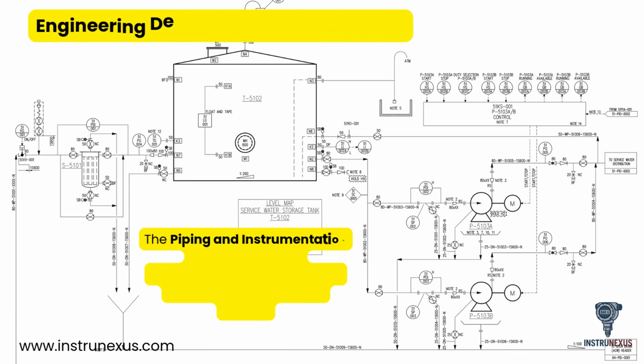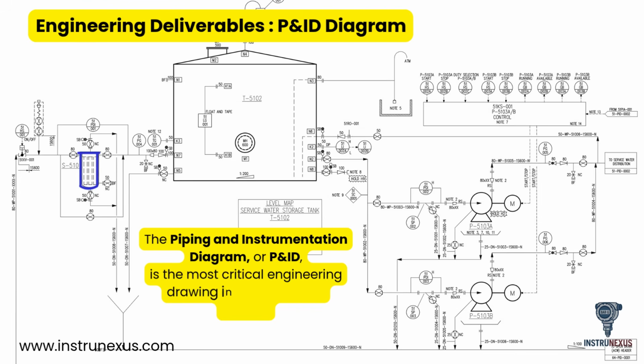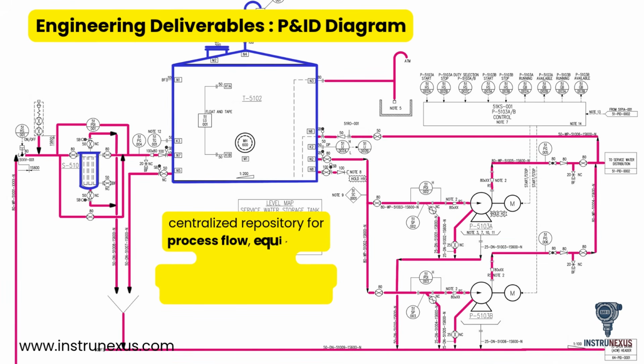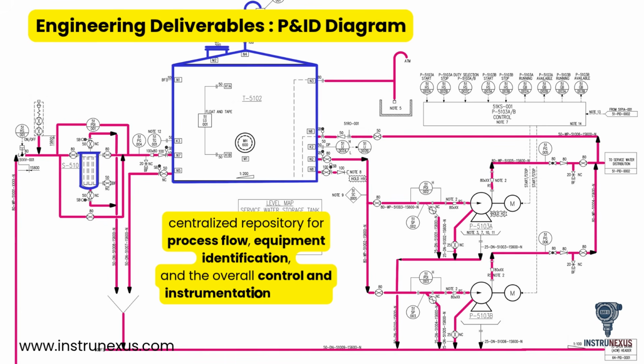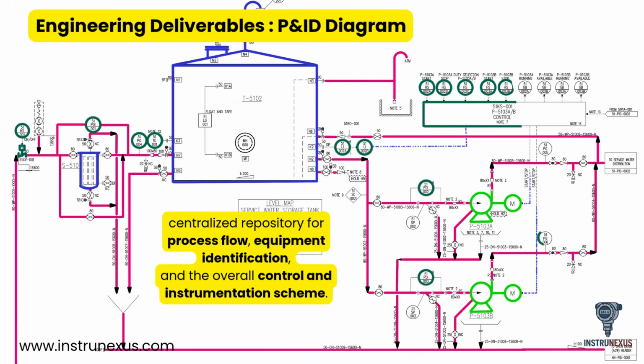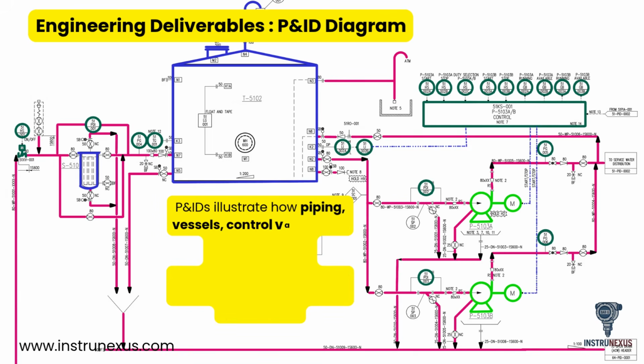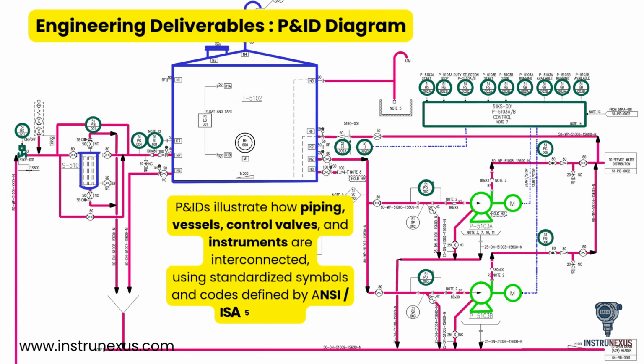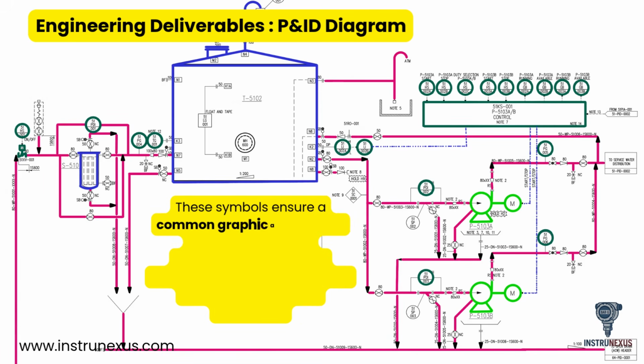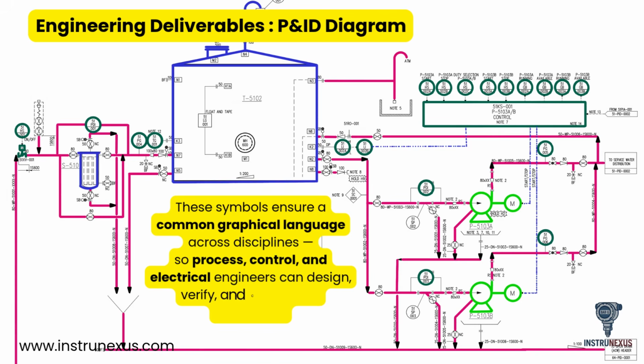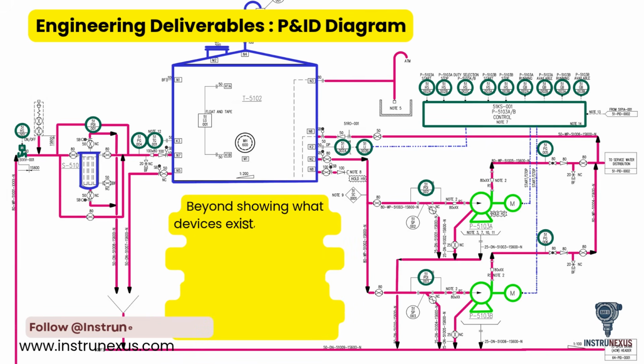The Piping and Instrumentation Diagram, or P&ID, is the most critical engineering drawing in any industrial project. It serves as the centralized repository for process flow, equipment identification, and the overall control and instrumentation scheme. P&IDs illustrate how piping, vessels, control valves, and instruments are interconnected, using standardized symbols and codes defined by ANSI/ISA-5.1-2024. These symbols ensure a common graphical language across disciplines, so process, control, and electrical engineers can design, verify, and collaborate seamlessly. Beyond showing what devices exist, P&IDs reveal how they interact.